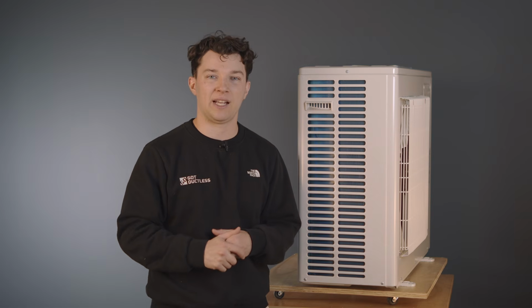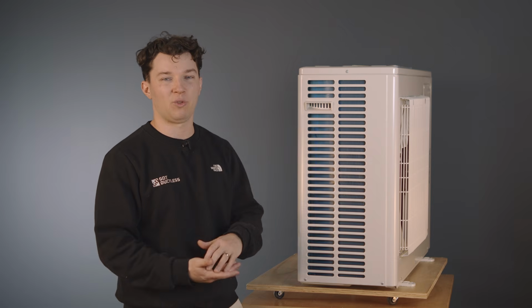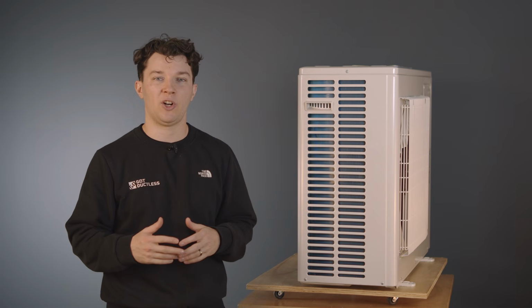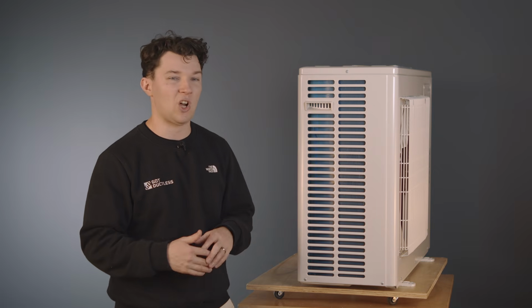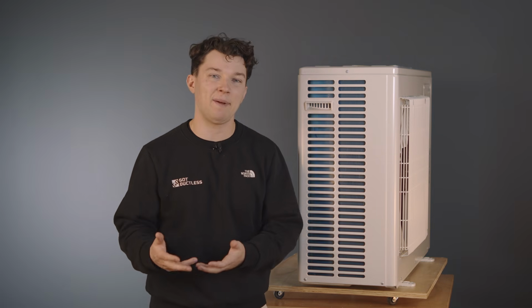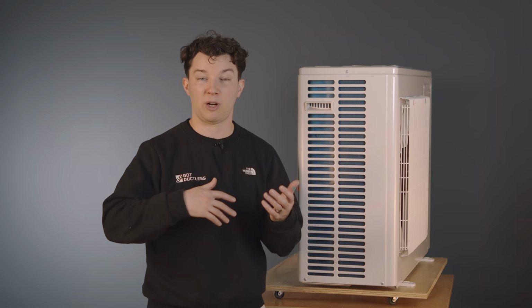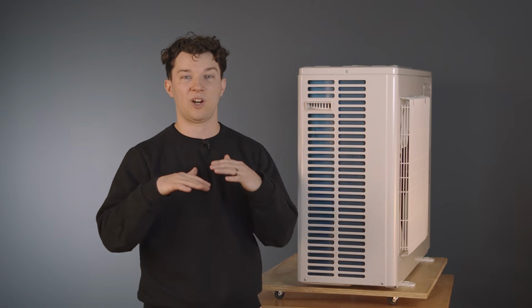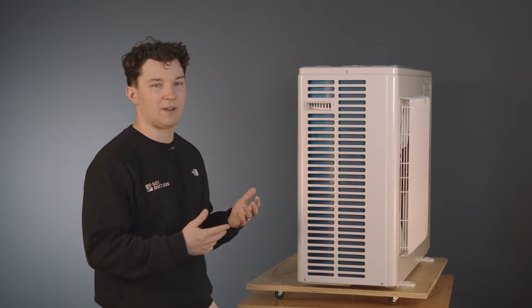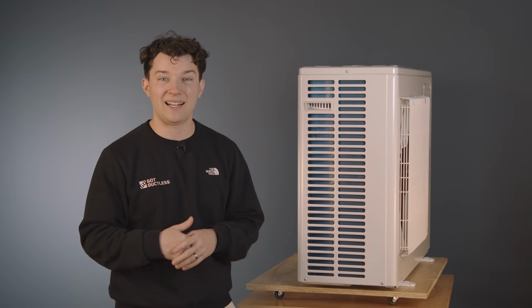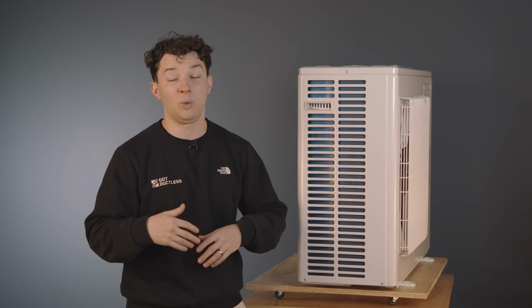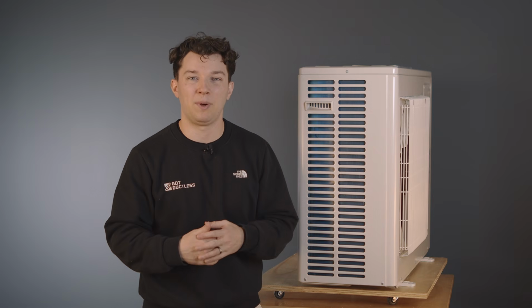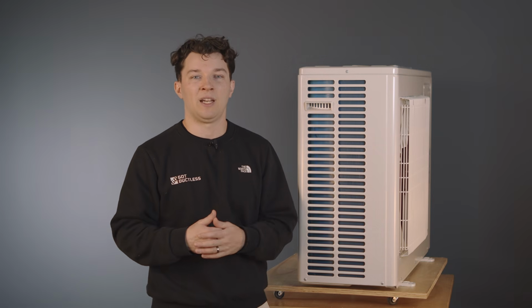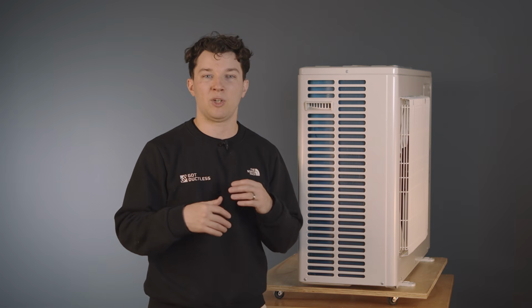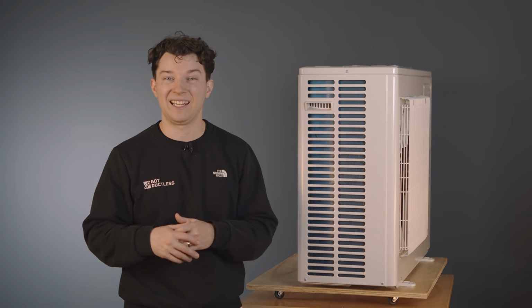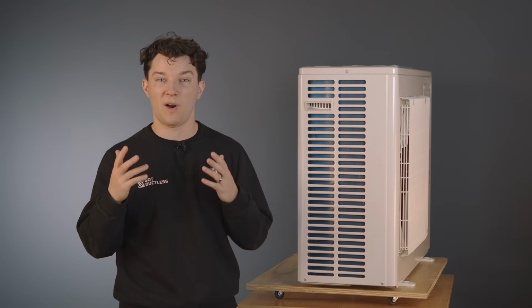We sell, at Ductless.com, 12-inch stands that have the unit raised off the ground 12 inches, or you can install it on what we call snow risers, which is 4 inches off the ground, which can be installed then on a cement block, or if you're installing it on the ground, we recommend using a plastic pad and then using the snow risers to raise it off the ground. Both are great options. This is a versatile outdoor unit that only weighs 119 pounds, and so you're able to do it either way. We like to always install it on the wall, but we typically recommend it if it's masonry, if you have a little bit more blocking. Sometimes when you're installing on vinyl siding and you're hanging off the wall, it can vibrate the wall, so we just want to avoid that.